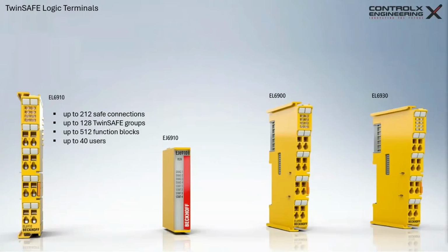This terminal can establish 212 safe connections to other devices. What counts as a connection? A connection is one instance of a safe communication channel between the EL6910 logic terminal and another device. These can include safe input terminals, safe output terminals, drives with integrated safety modules, and remote IP67 safety modules. This allows us to deploy large distributed safety systems with multiple safety islands and design complex machines with many safe I/O points. It is one of the reasons the EL6910 is considered Beckhoff's flagship safety controller.